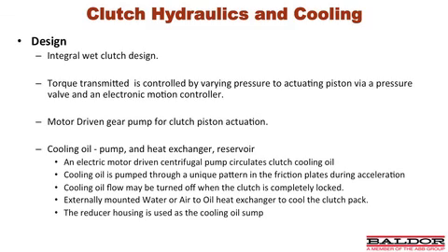The cooling oil is pumped through a unique pattern in the friction plates during acceleration, and we'll show you an image of these clutch plates in just a moment. The cooling oil flow may be turned off when the clutch is completely locked, and the pump will do this automatically. An externally mounted water or air-to-oil heat exchanger is used to cool the clutch pack. The reducer housing is used as the cooling oil sump.